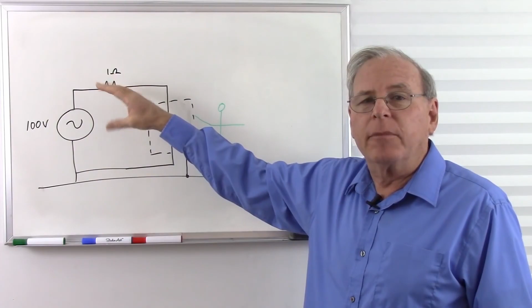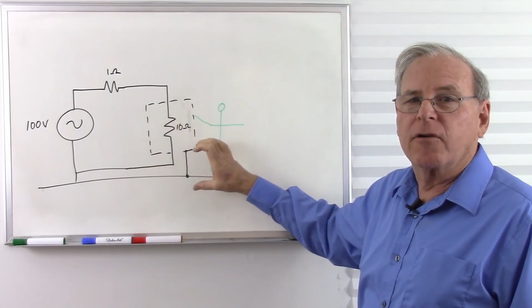So when we ground something, we're taking advantage of the inherent resistance in the system, so that when we do have a short, we get the high current through here, but the resistance here is so low that the resistance of the system overwhelms it, and I lose so much voltage going through this resistance, I have nothing left over across the resistance of my ground. Therefore, I don't have enough voltage to push the current through me to be dangerous.